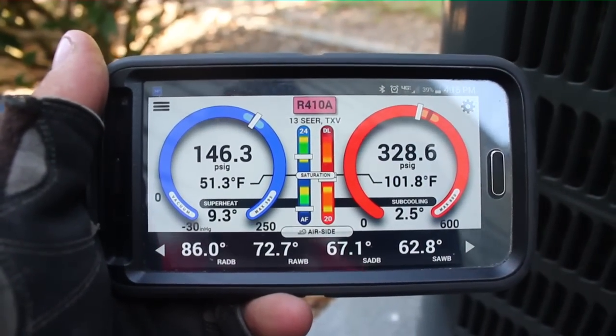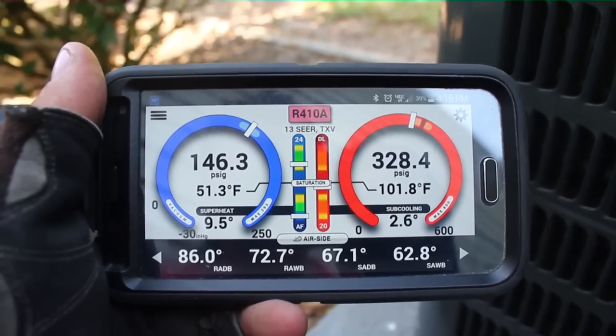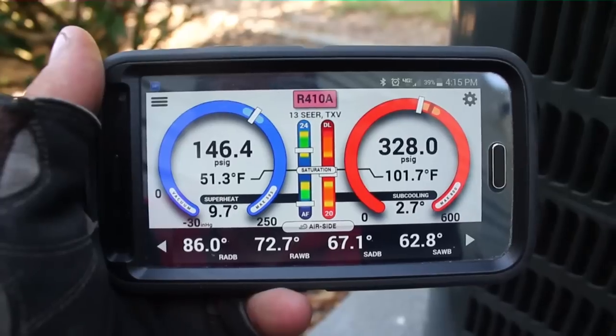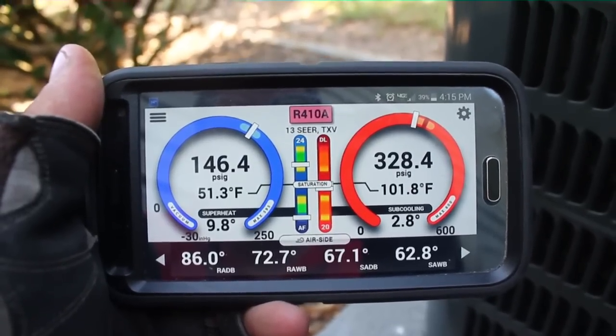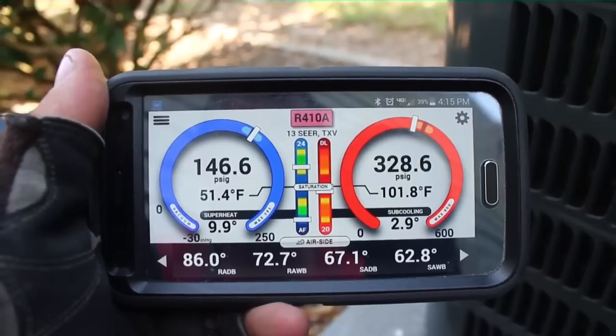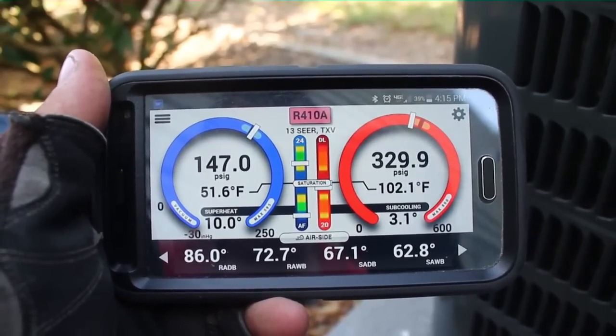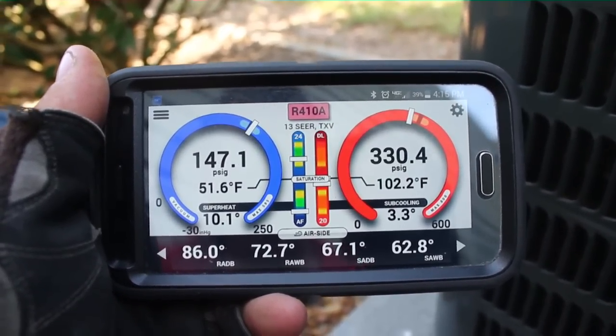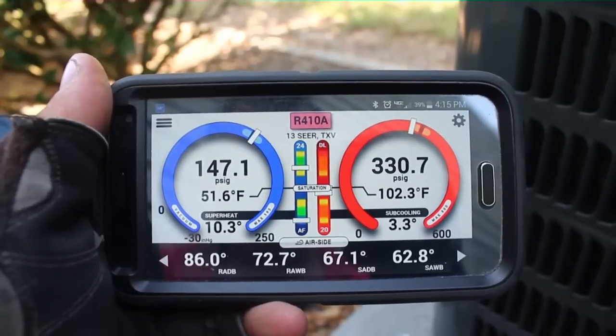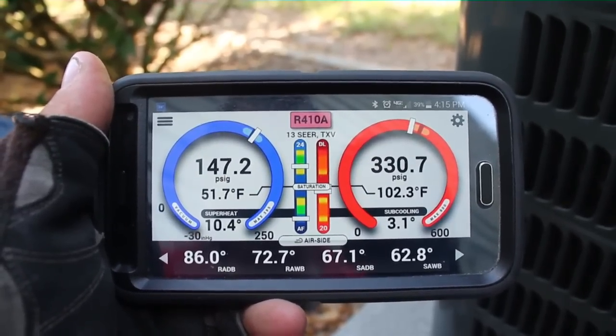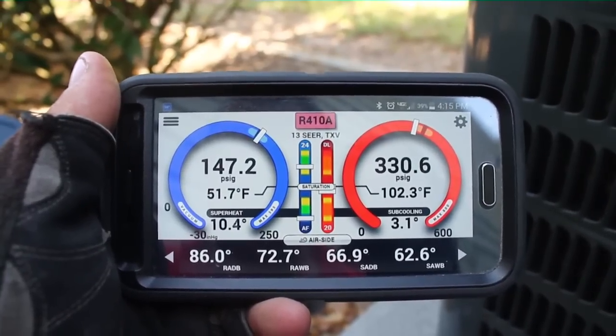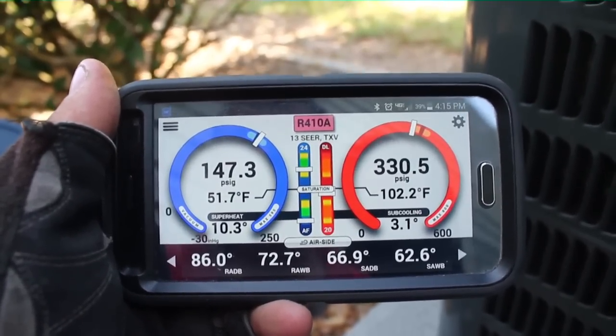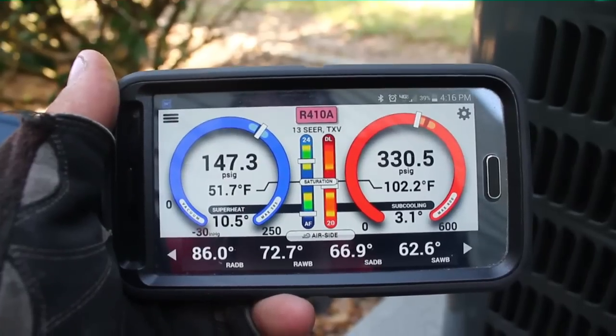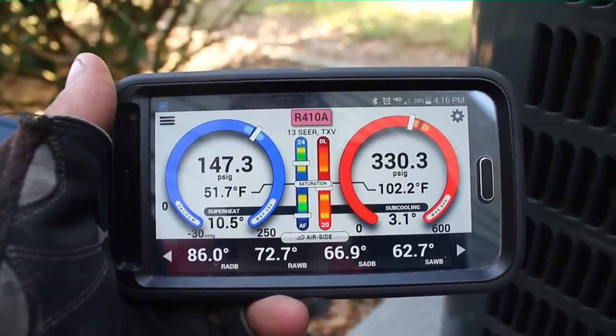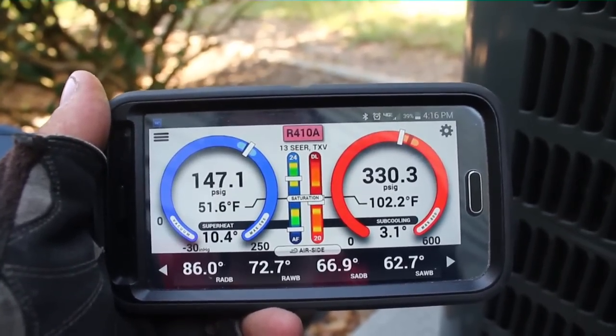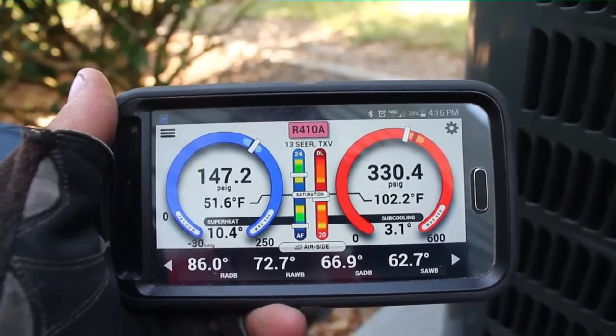It looks like I didn't have to cut the TXV or adjust it back. Right now we have 9.7 degrees of superheat. The TXV is actually regulating the superheat, cutting back the refrigerant flow. As you see, as it cuts it back, we have 10 degrees of superheat now. We get a greater subcooling. The TXV is restricting the flow of refrigerant into the evaporator, forcing it to back up into the condenser. Get a higher head pressure, higher subcooling. Basically doing its job. So we'll see.